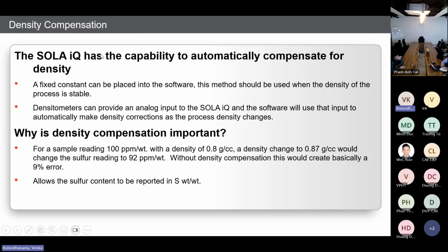Also, our SOLA IQ has the capability to automatically compensate for density. A fixed constant can be placed into the software. This method should be used when the density of the process is stable. Meaning, if the customer's process has a stable density, they can use a fixed density value. They have to calculate the process density and plug the value into the analyzer. Once they plug it in, the analyzer output will be compensated with that density value and give the ppm weight per weight basis sulfur result.